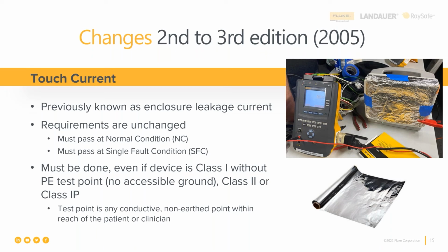And so here's how that current is going to flow and why we use aluminum foil. In electronics, a component that has a conductor, an insulator, and another conductor all in that one component is called a capacitor. A capacitor will carry current flow. And so what we have formed inside this plastic shrouded medical device is conductors and current flow inside of it. And we as human beings are conductors. Yes, we are conductors, not insulators. And therefore, the plastic being an insulator, when we put our hand on the outside of that medical device, current will flow, and we need to know how much, under what conditions, and where is it flowing. That's the questions we need to answer.